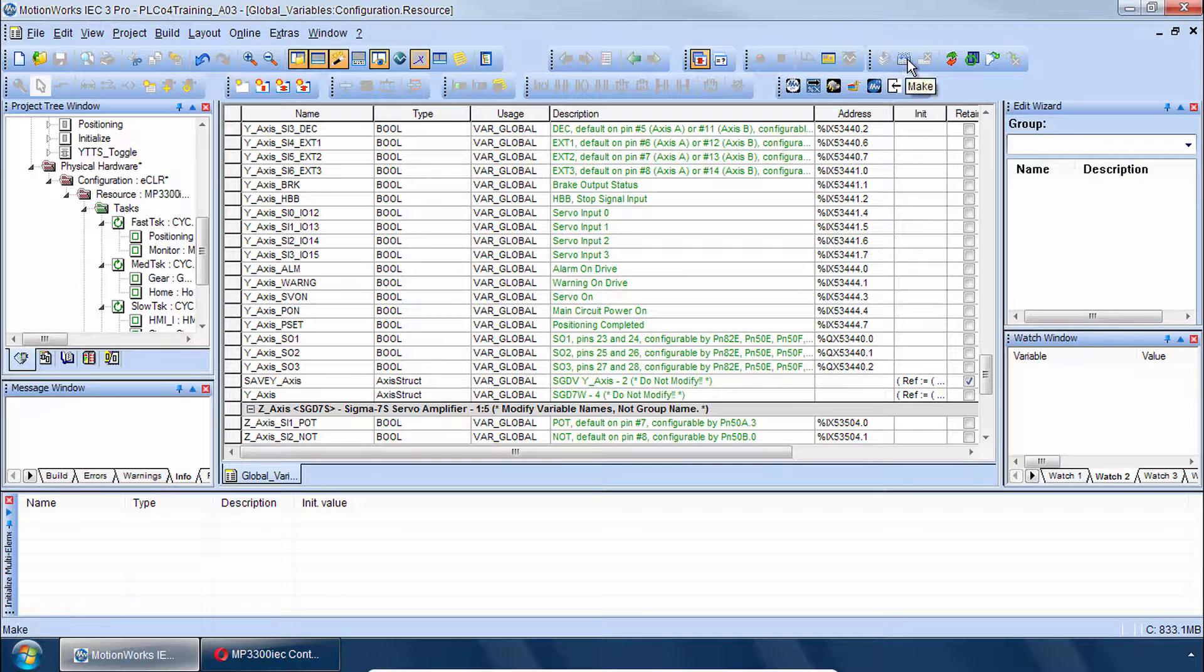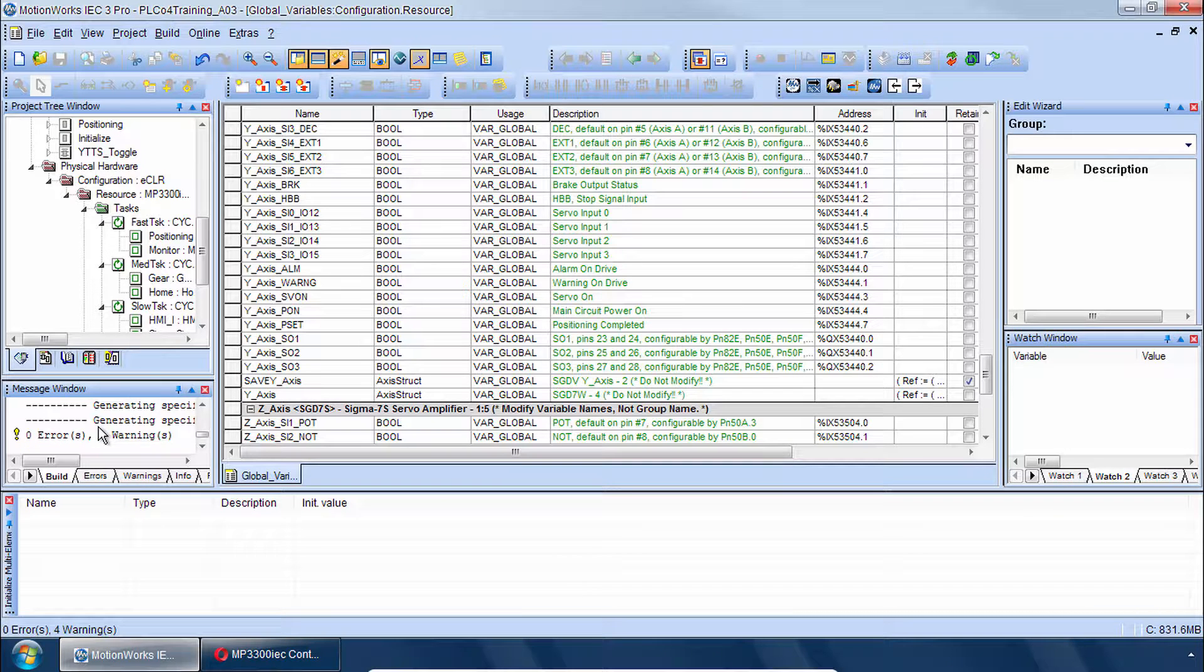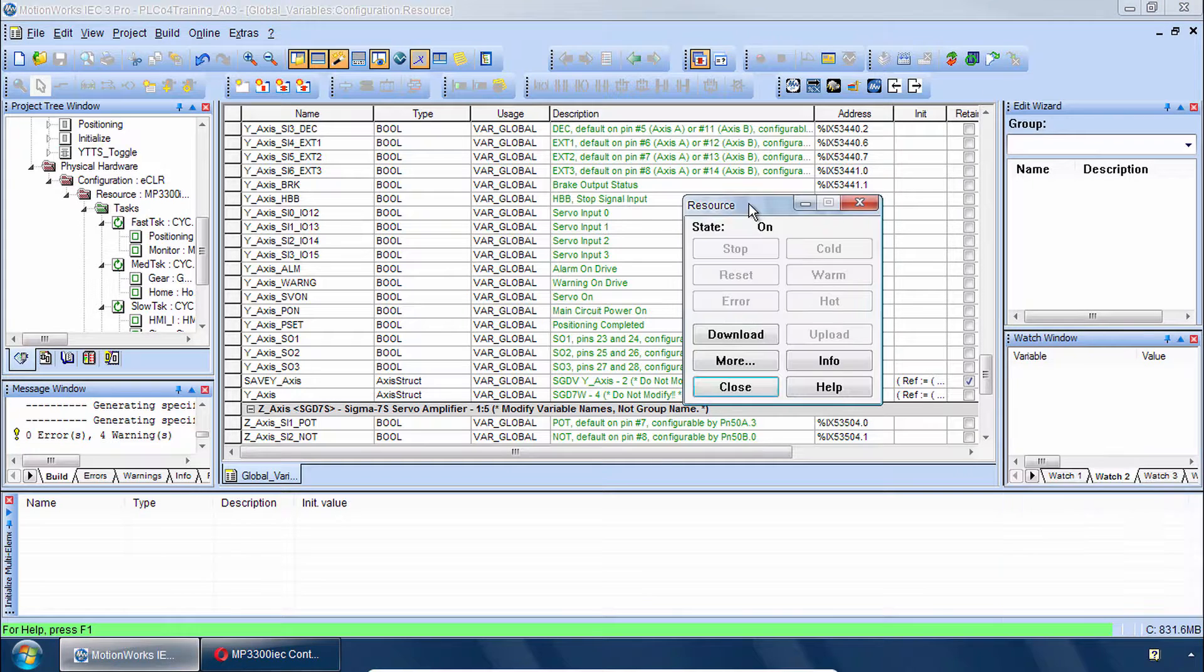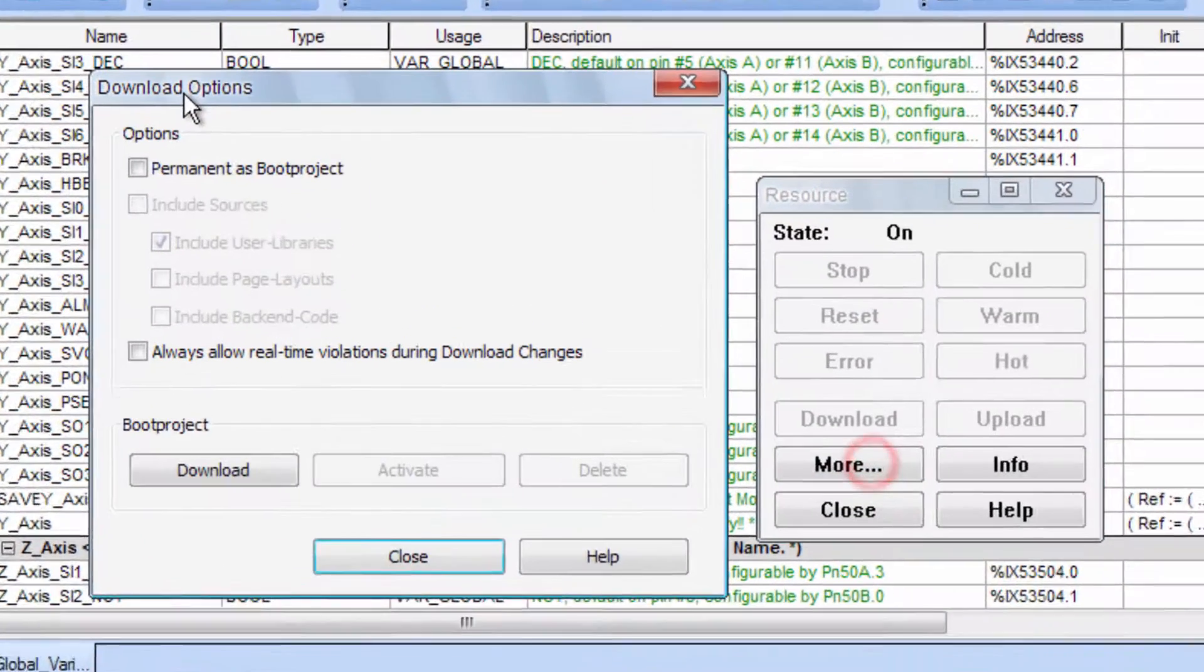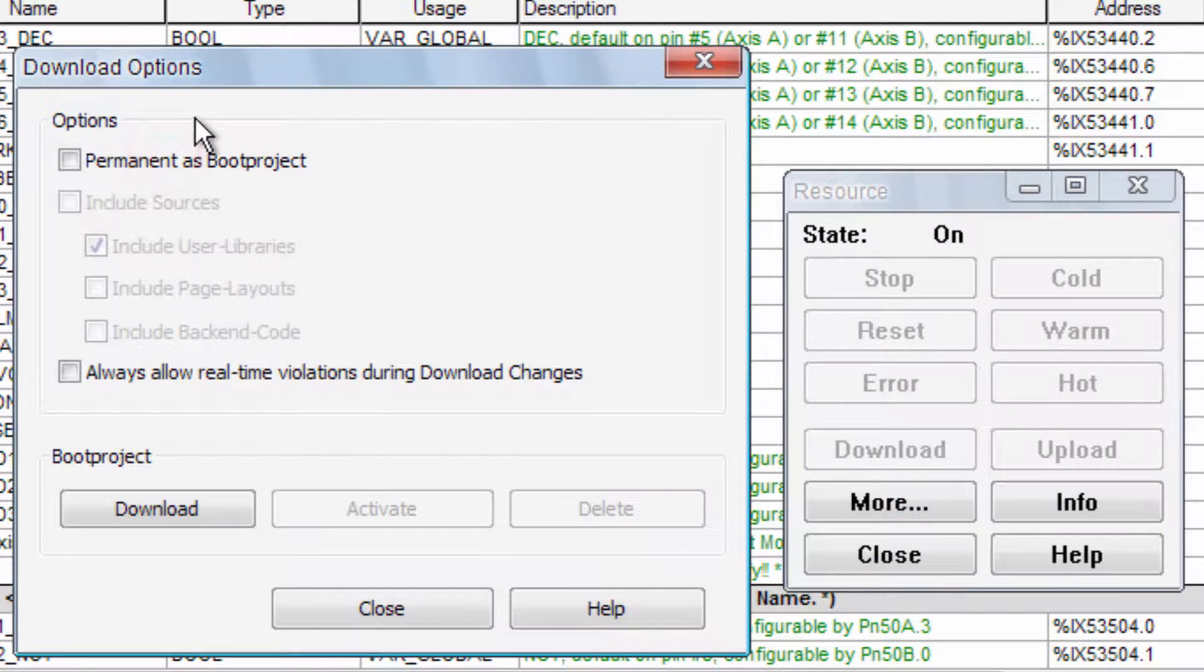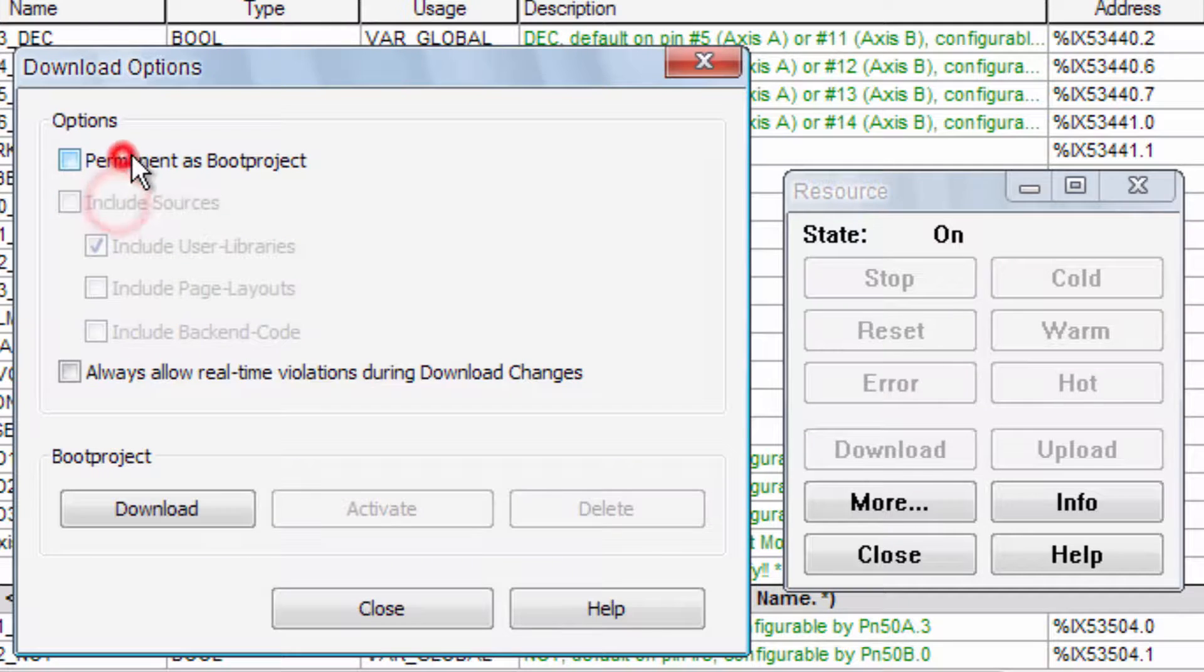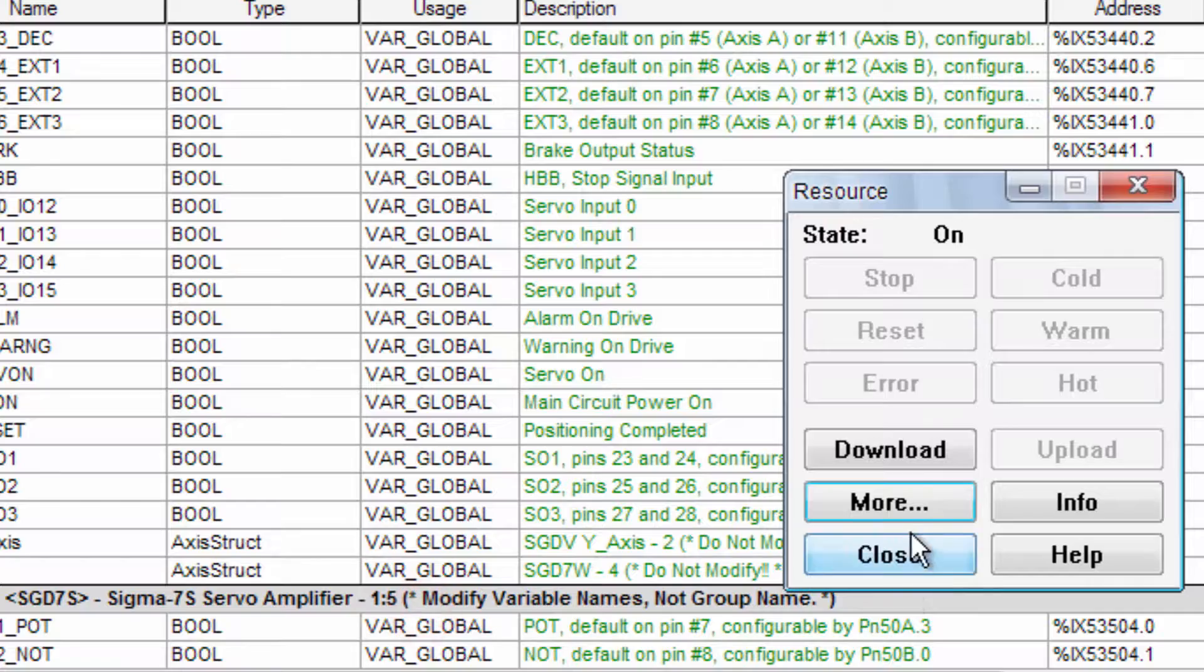And make this project. You expect to have zero errors since we've not changed anything in the project. Let's go to download this through the project control dialog. And for this controller you might want to click the more button first. And during development I tend to just save some time by unchecking permanent as boot project and include sources. It does mean that if you reboot the controller you'll have to download again. That's about it. So set those options however you want. Close it and then click download.